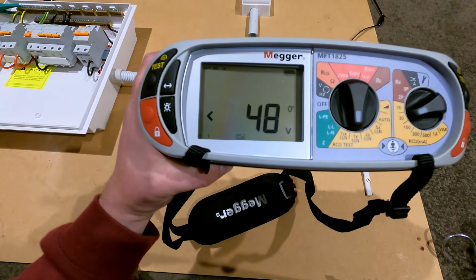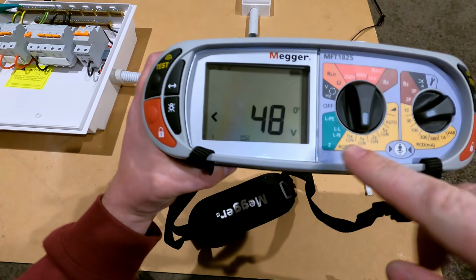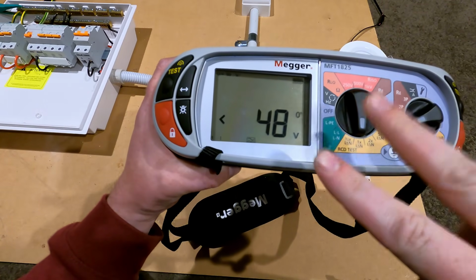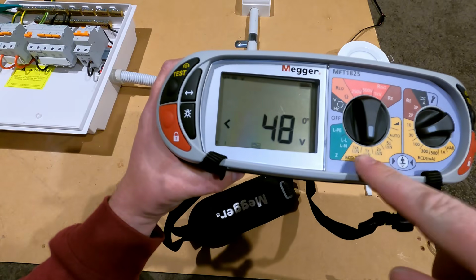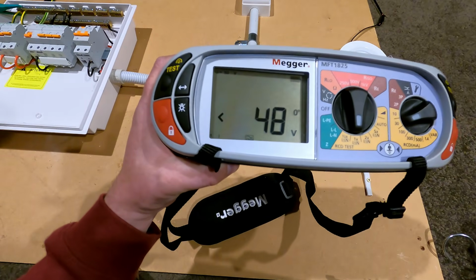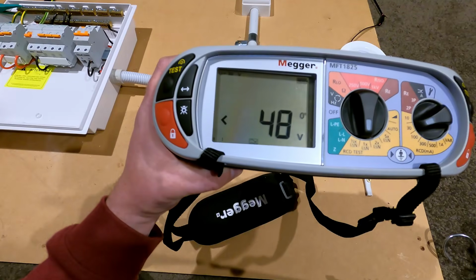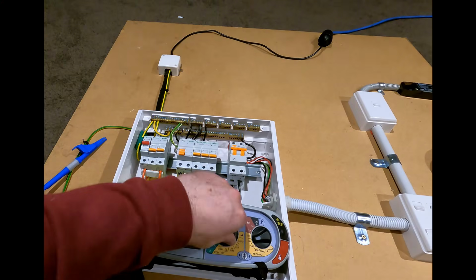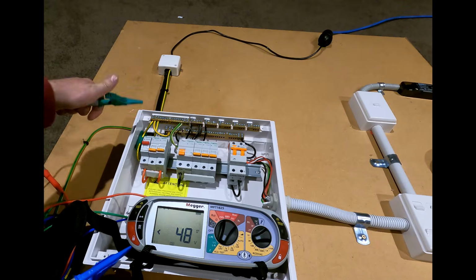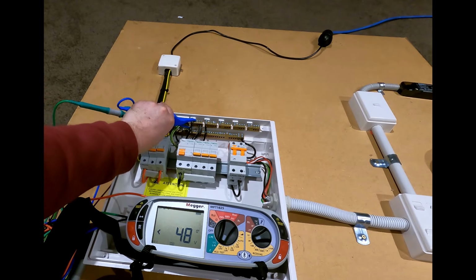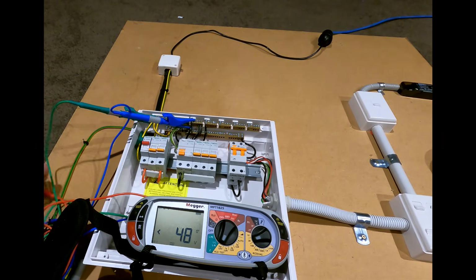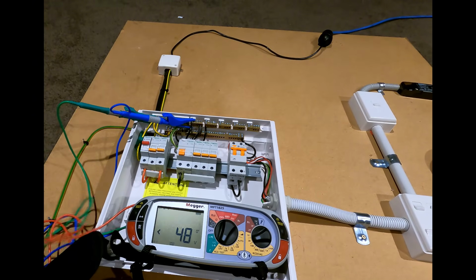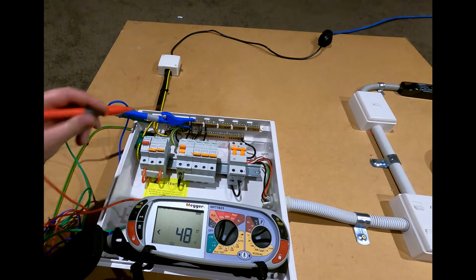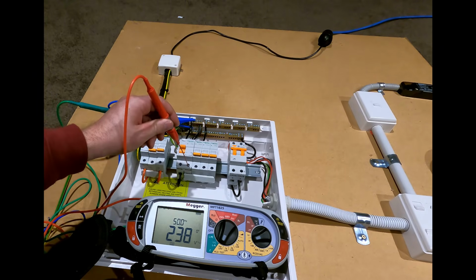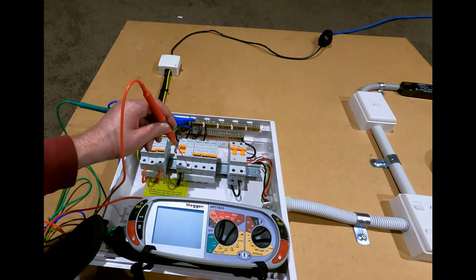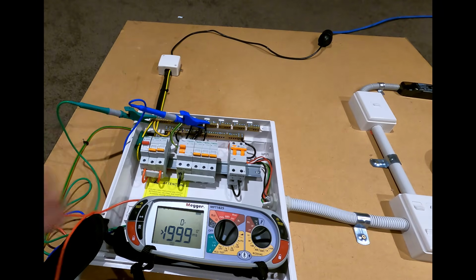For this video, to save time, I'm only going to be doing these tests once for the RCD and once for the RCBO, so once per unit, but only at the 0 degrees function, which is default. So I won't be doing the 180s. The first test we're going to do is our half trip. Put our earth on the earth bar, neutral on the load side. So we're going load side of the RCDs here. So the first RCD we're testing is this one here. And then with the probe, we go on our load side phase and we'll hit the test button. No trip. Do the same for the RCBO.